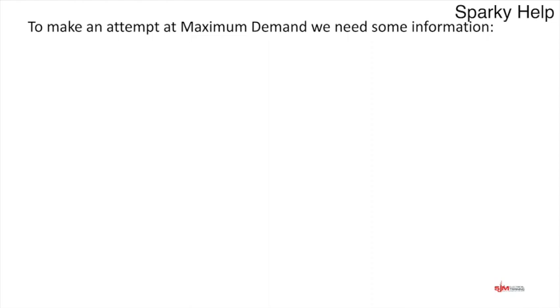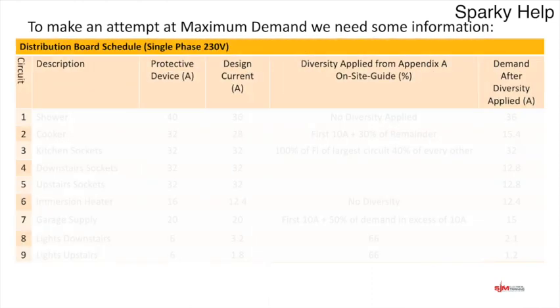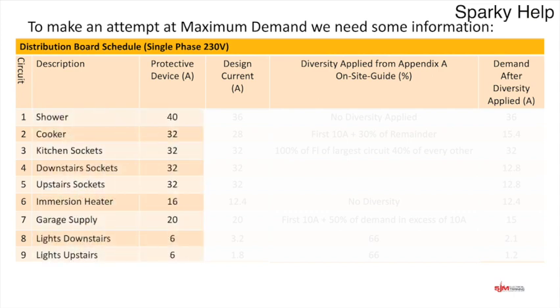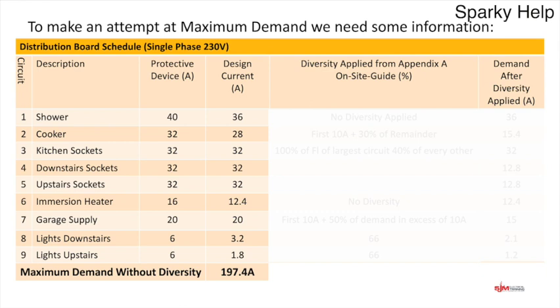Let's work through a typical domestic installation. I've put together a standard distribution board schedule — a single-phase installation with circuits 1 to 9: shower, cooker, kitchen sockets, downstairs sockets, upstairs sockets, immersion heater, garage supply, downstairs lights, and upstairs lights, with their protective devices and design currents shown. Without any diversity applied, adding all the design currents gives a maximum demand of 197.4 amps, which is obviously quite large, so we can apply diversity from the On-Site Guide.